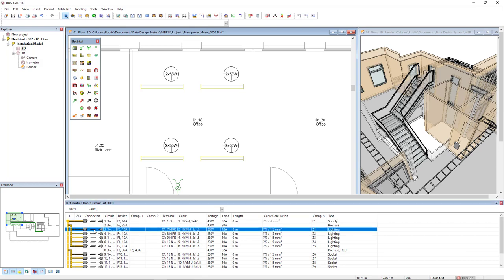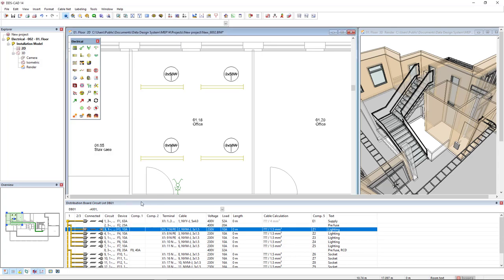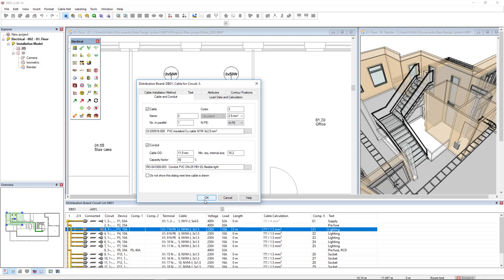Now I will select the first circuit for lighting as we can see here in the text column. I will right click and select the option draw cable. Here we see the cable that we have predefined. We can change the size. For example, I will select 2.5 square millimeters and I can also activate the conduit and click OK.